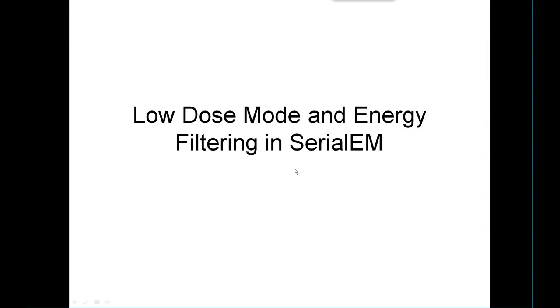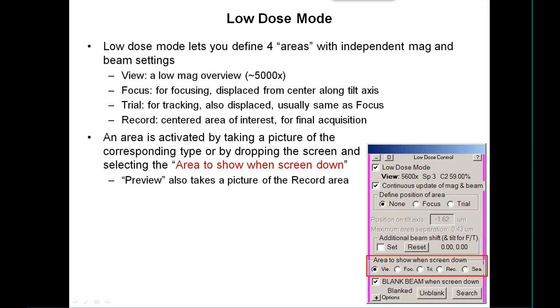We're going to talk about low-dose mode and a little bit on energy filtering, since that's integrally part of doing cryomicroscopy. Low-dose mode lets you define four different areas, each with independent magnification and beam settings. They're named the same as the default names for camera acquisition because they're tied to these modes: view, which is usually set up for a low-mag overview; focus, for focusing off displaced along the tilt axis; trial, also displaced; and the record area, which is where you really want to get your data from and are trying to protect the most from the dose.